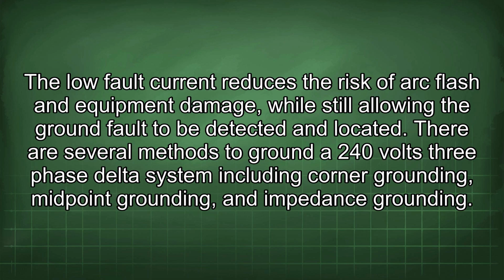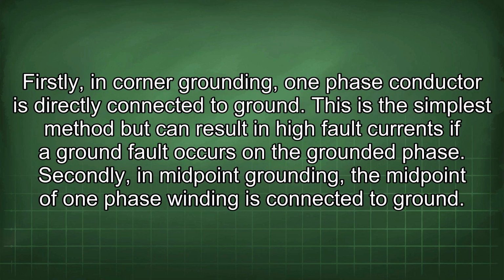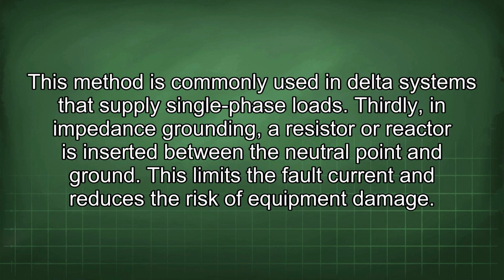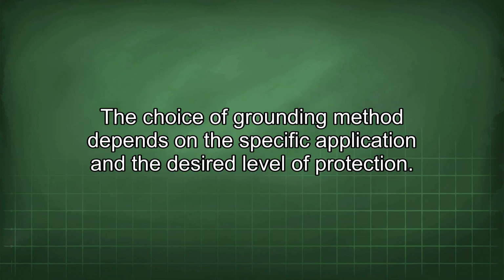Firstly, in corner grounding, one phase conductor is directly connected to ground. This is the simplest method but can result in high fault currents if a ground fault occurs in the grounded phase. Secondly, in midpoint grounding, the midpoint of one phase winding is connected to ground. This method is commonly used in delta systems that supply single-phase loads. Thirdly, in impedance grounding, a resistor or reactor is inserted between the neutral point and ground. This limits the fault current and reduces the risk of equipment damage. The choice of grounding method depends on the specific application and the desired level of protection.